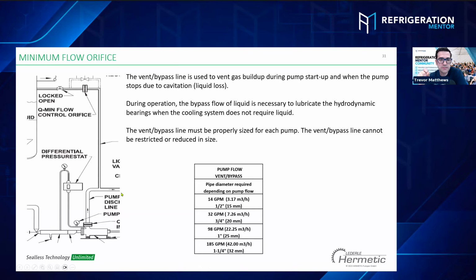For example, I say the system is not demanding too much liquid, and the pump starts getting high pressure on the discharge and is going to stop for high differential pressure. Plus flash gas, those bubbles can go direct to your control valves and to the Teflon seats of your solenoid valves, and damage the solenoid valves' Teflon seats at some point.